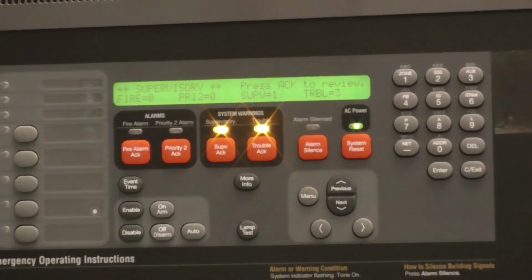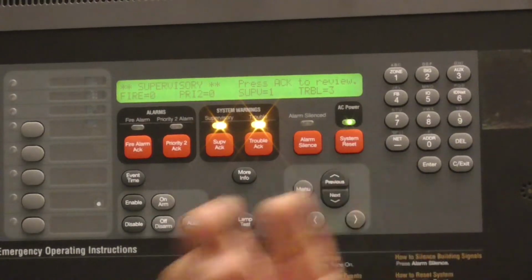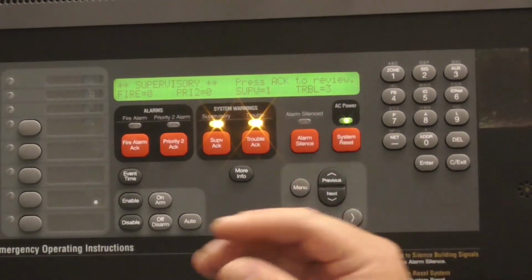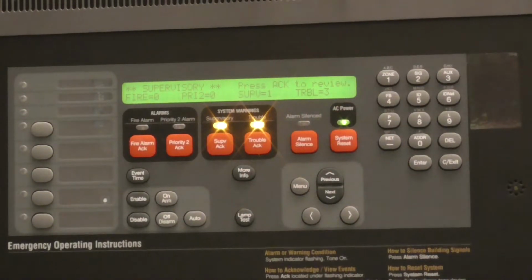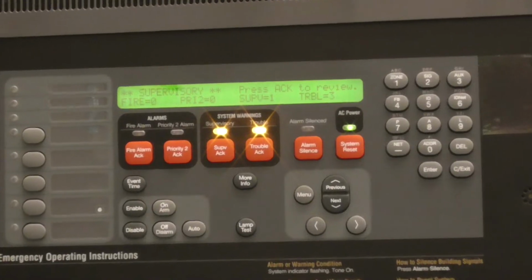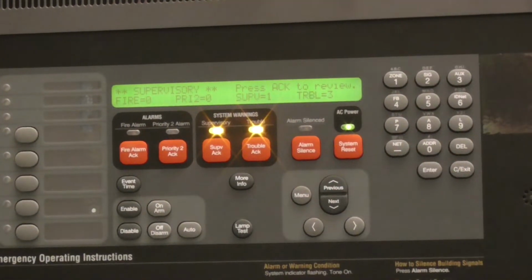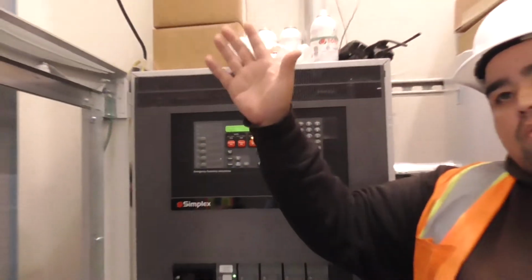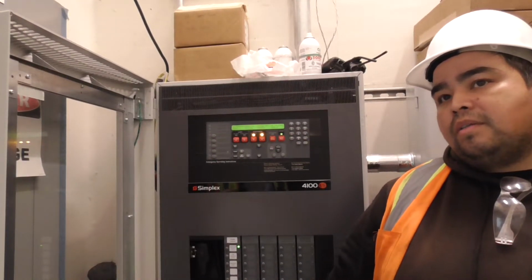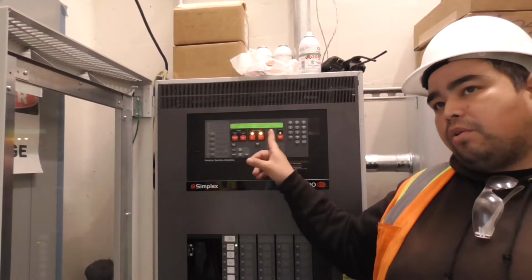Anything other than that, when it comes to anything that goes into alarm, it's going to be specific. They're going to see it exactly like it comes up on this display. So if you have a card problem or something like that, they'll get the same issue. It'll say card trouble status at the main computer at PD. It won't say power supply missing to that detail. You'd actually have to come to the panel to look at what it is.